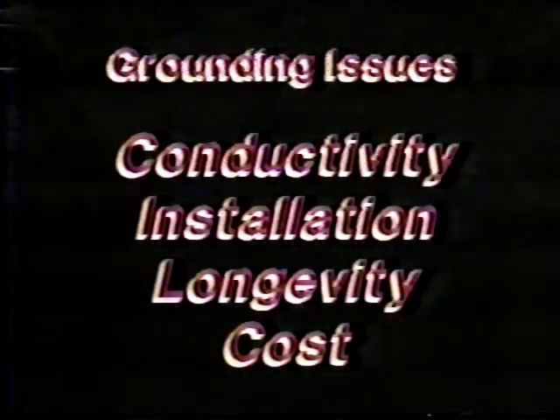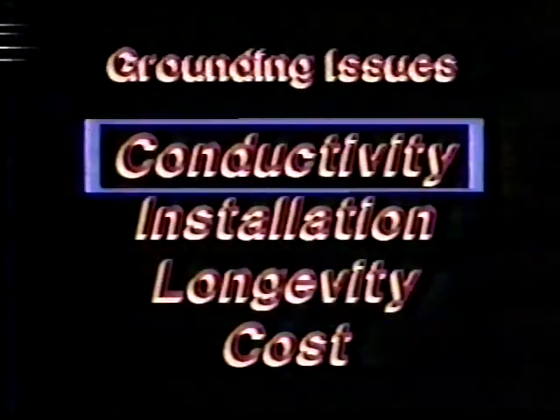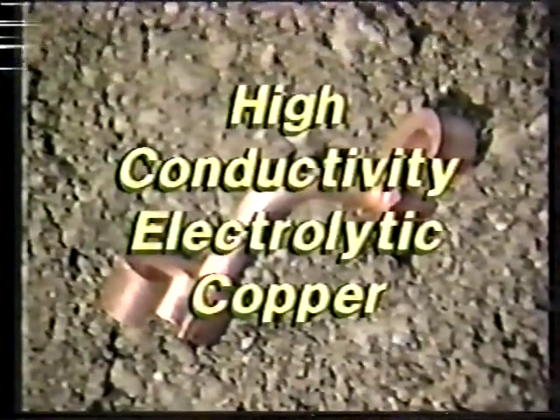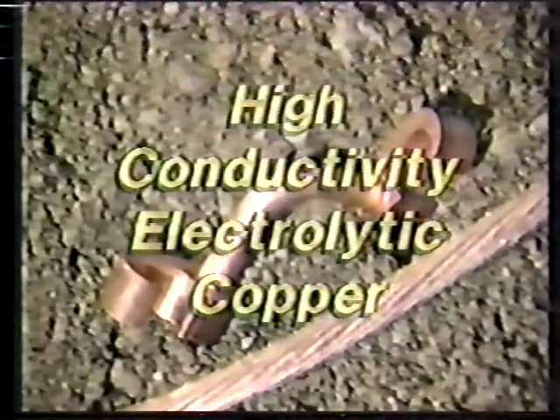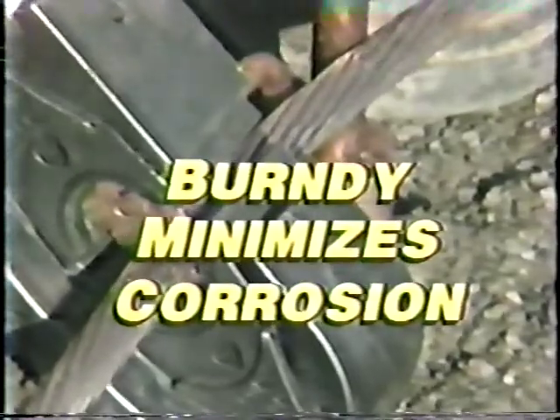For a moment, let's examine the key issues facing today's grounding systems and how the Burndy high ground compression system addresses these issues more effectively than exothermic type products. High ground compression connectors are made of high conductivity electrolytic copper, the same material as the copper ground cable itself. In addition, each connector is pre-filled with Burndy's unique Penetrox E compound, a synthetic oxide inhibitor with copper filings to help seal the connection and prevent corrosion in below-ground installations. By using the same copper material, the possibility of corrosion due to dissimilar metals is virtually eliminated.